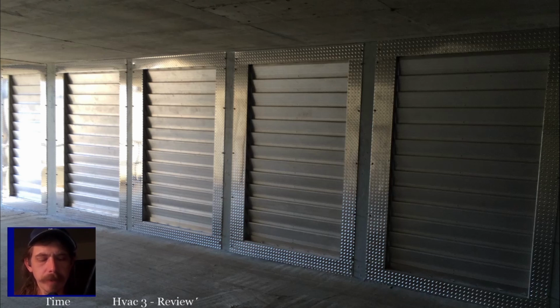Zone valves are there to control zones. Just like a zone damper, a zone valve is going to control water flow to any individual zone with the thermostat so that only the ones that are calling for heat get heat. And then there's a section on zoned hydronic system operating sequences here. You're more than welcome to look at that so that you understand the operating sequence.